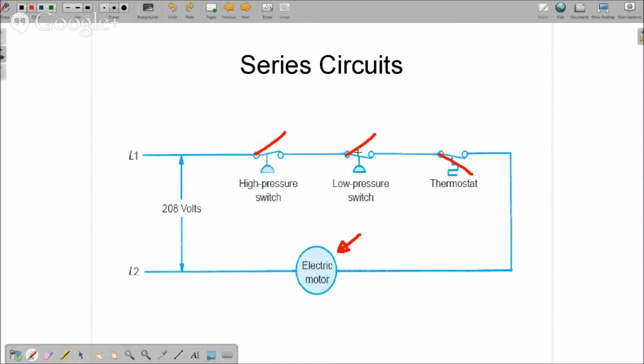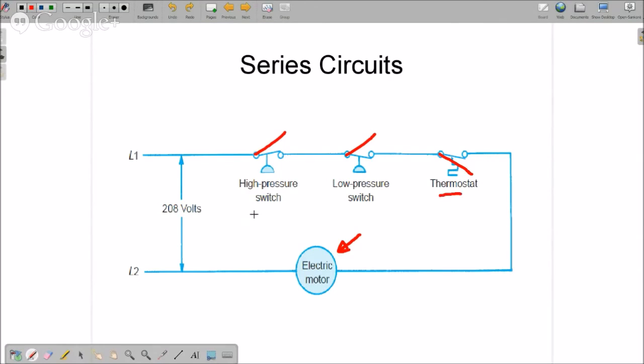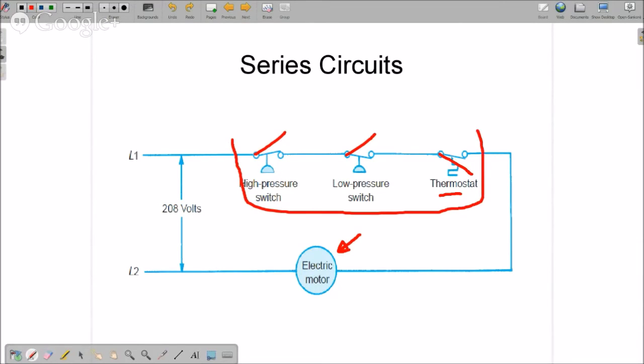A lot of times they are safeties and overload protection that if there's a high pressure situation, it'll stop the motor, a low pressure situation stops the motor, and then some controls over here. And all of those controls for an individual load are wired in series, which means any one of those that opens or breaks stops that load from running.